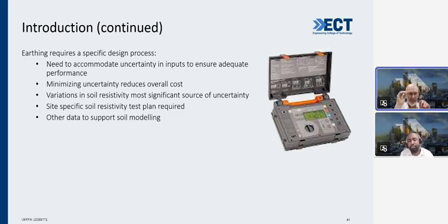Thanks, Samkela. Thank you very much for your words of wisdom there. Really appreciate it. Obviously, earthing requires a specific design process, and Samkela has mentioned some of those points. If you're putting earth rods into the ground, you need to watch out for the soil resistivity. There are a few slides here devoted to soil resistivity and working out what that is, and you need a plan, so I've put that in the case study. We'll quickly mention that, but it's quite difficult to come up with the right number, because it does vary quite a bit.